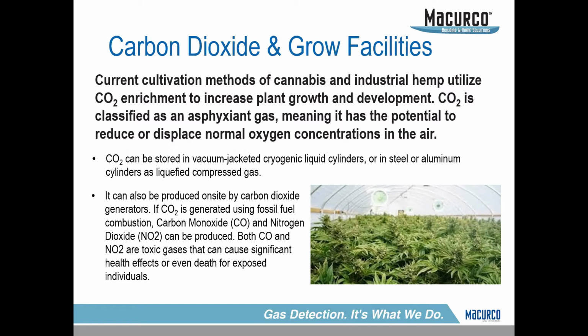The big thing we base that number off of is ventilation. There's a difference between a storage room of CO2 tanks and where the CO2 is actually being thrown into. Our connection points in the storage room are where we're going to monitor - if there's multiple storage points, connections of valves, turns, 90-degree elbows, whatever the case may be, we want a detector to be somewhat in that area. Now in square footage, if you're talking 100,000 square feet, we've got to measure it based on square footage, and that's how we would go about this.